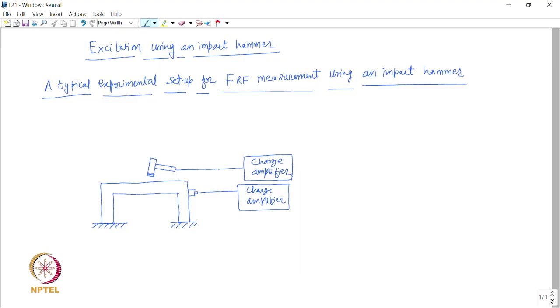The charge amplifier converts the charge signal into a voltage signal. This voltage signal from the charge amplifier is then fed to a data acquisition system or an FFT analyzer. If we are using an FFT analyzer, we require at least two channels for measurement, because we want to simultaneously measure the force signal as well as the response. So we require a dual channel measurement.